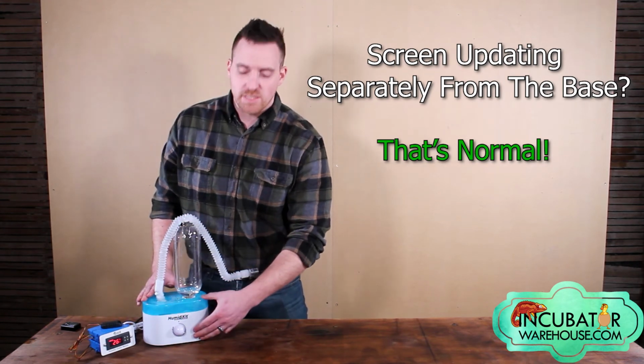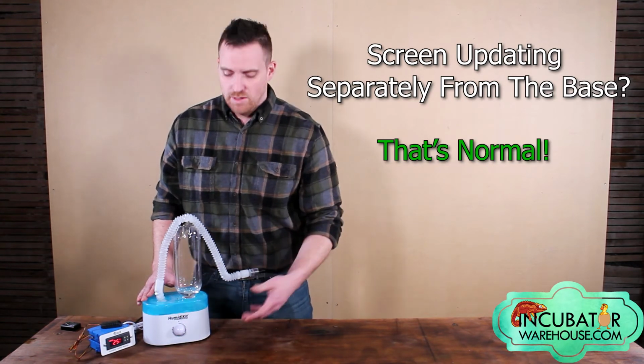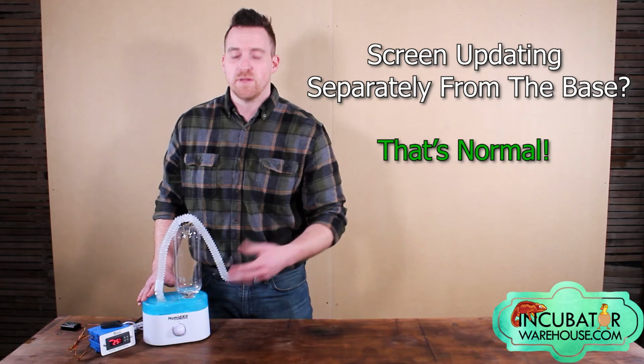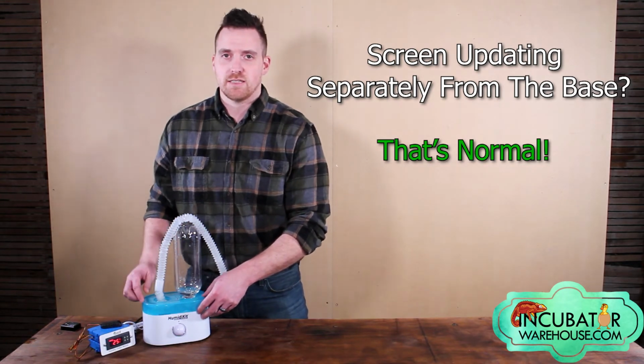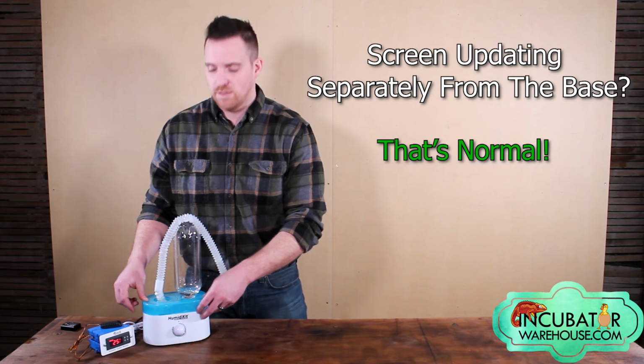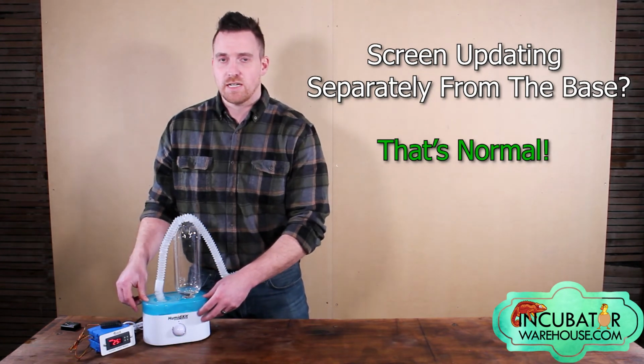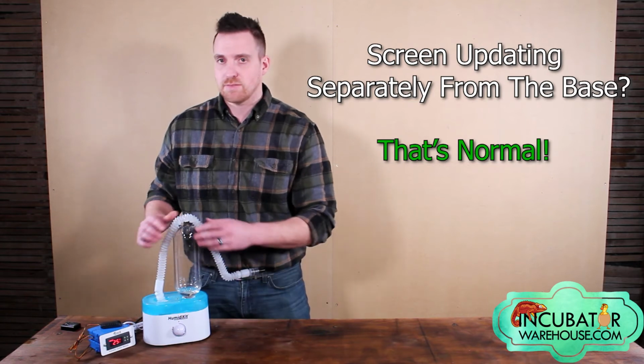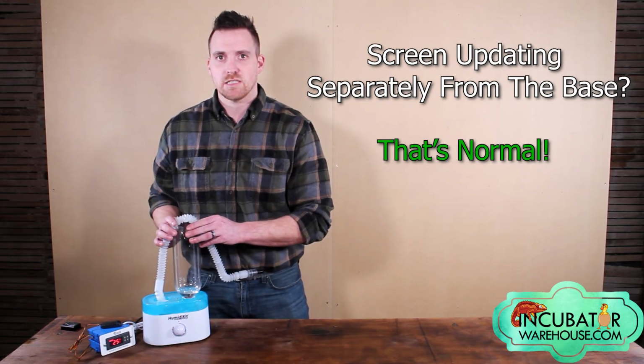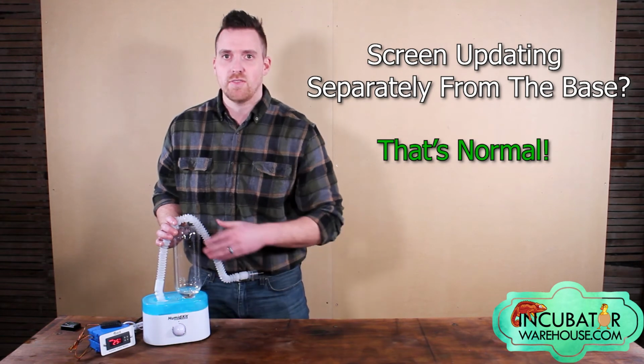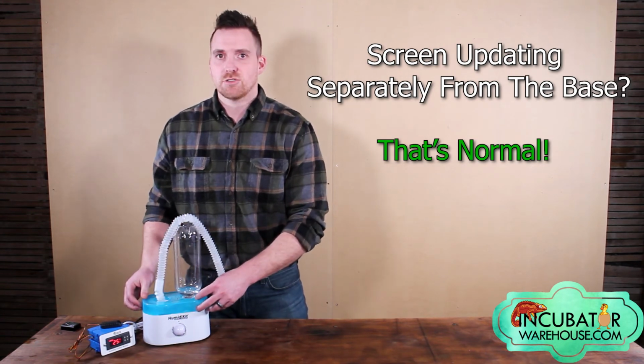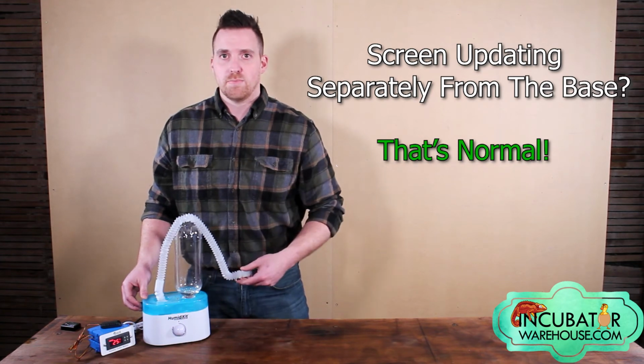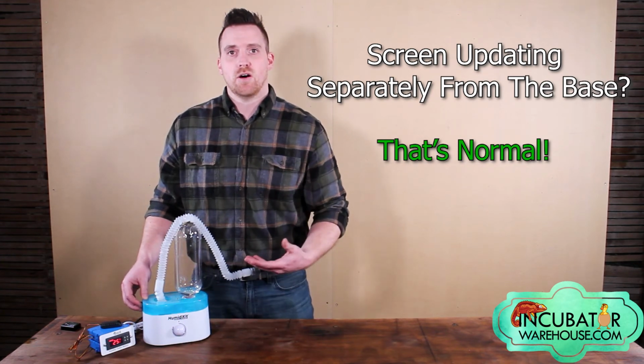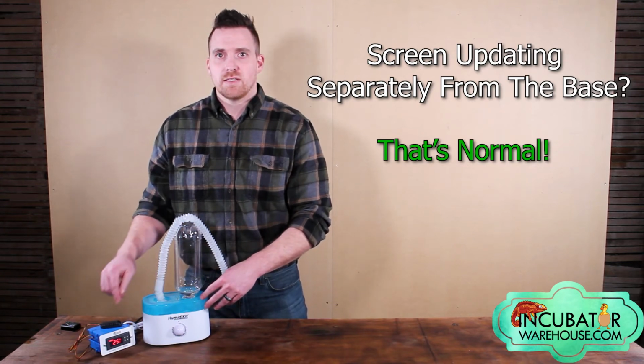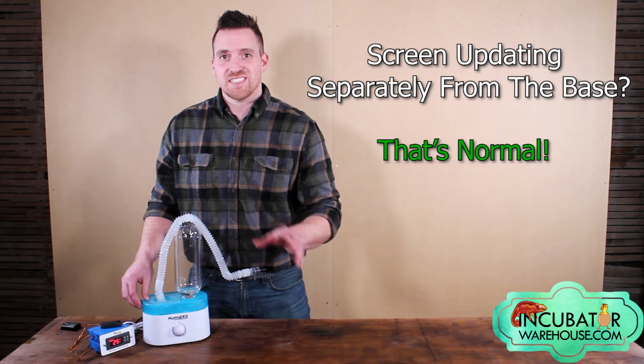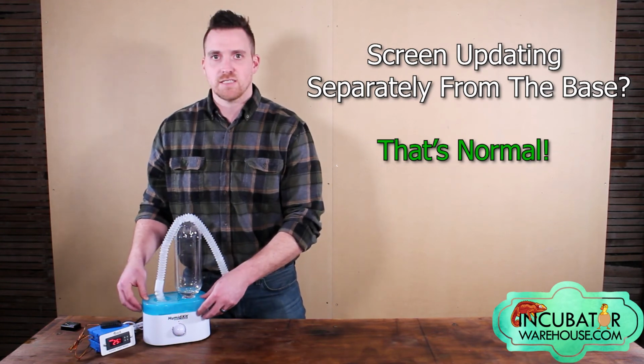But it has already been producing humidity to raise the overall level, and it might continue to increase for a moment. If it never stops increasing, this could be a potential problem with the sensor unit. Now on the opposite, as it goes down and it drops below the set point, it'll go down a percentage or so and the sensor will indicate a low humidity percentage and it'll turn on the Humidikit base. It might continue to drop a few more percentages while the Humidikit base works to produce enough humidity to bring the overall level back up. Over time, these swings will level out as the unit stabilizes and the humidity becomes more constant throughout the entire incubator.